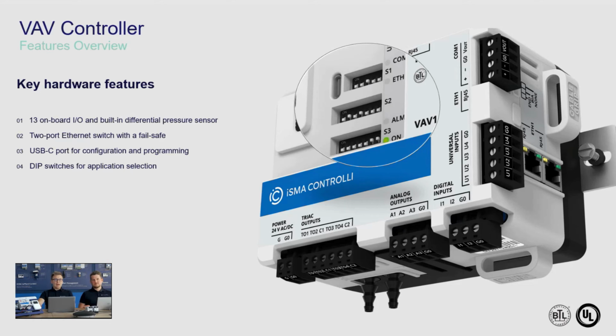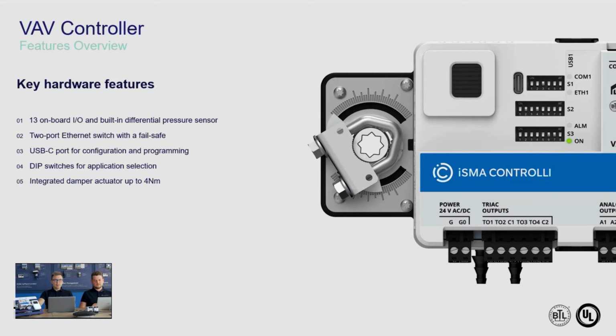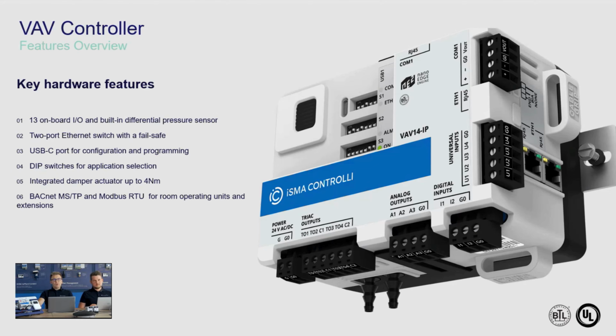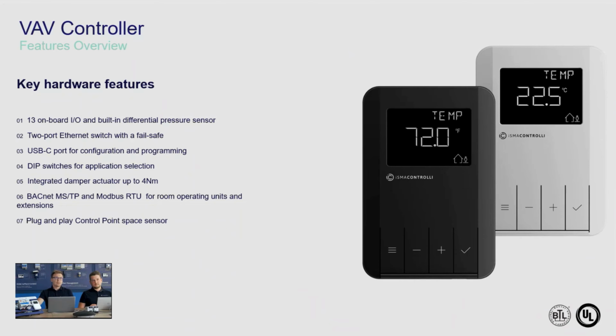The DIP switches allow you to make a configuration of the application. So with only DIP switches, you can configure, set up, and commission the controller. We have the integrated damper actuator with the torque up to 4 Newton meters. From the communication point of view, we have the BACnet MSTP, BACnet TCP IP, and dedicated ports to connect the room operating unit and some kind of extensions. Which room operating unit? We have the CPVAV, which is the plug and play control point space sensor.